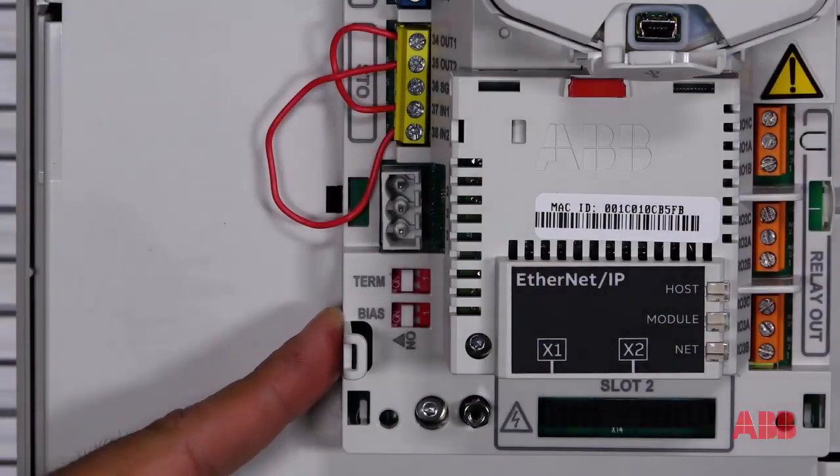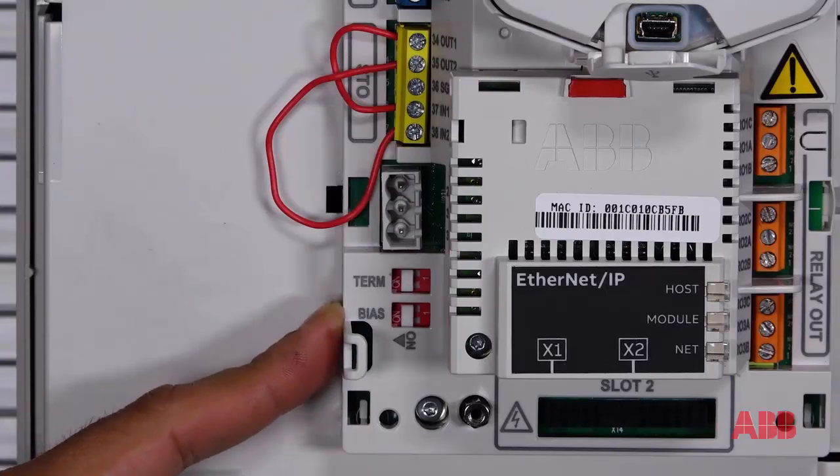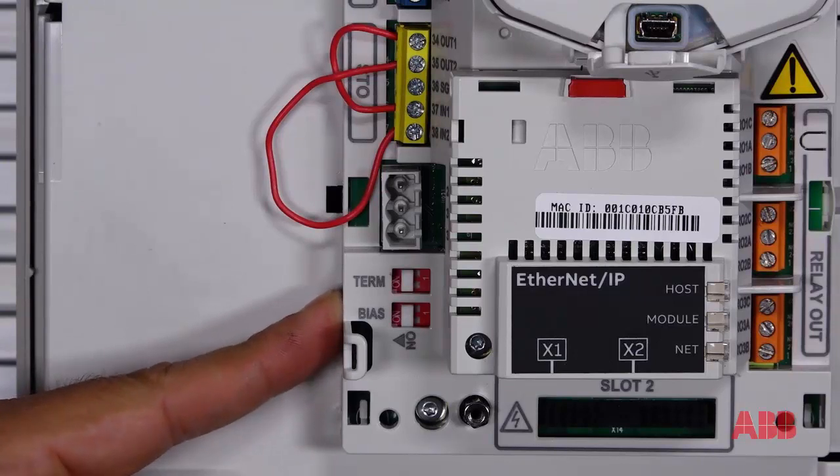Now, before putting the covers on, you want to make sure that the last drive of your network has both their termination and their BIAS switches on. Otherwise, you will not be able to have communication.